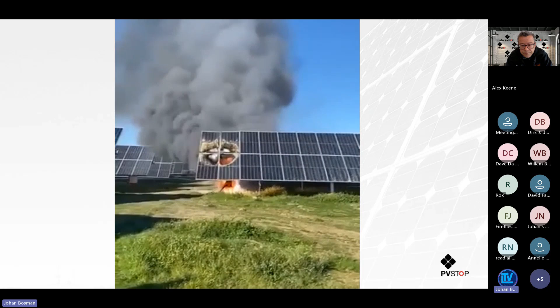So a short clip, but very informative and instructive one. I wanted it to play in silence so you could hear the sound. Hopefully that sound of the electrical fire came through quite clearly. It's an aggressive fire. It will consume and carry on consuming until there's nothing left to burn. You're looking at a significant electrical arcing event, which is dangerous and risky from an electrical perspective, but it's also a significant thermal event. You're talking about temperatures upwards of probably in the region of 12,000 to 14,000 degrees Celsius. It's like touching the sun. This is a very destructive component.